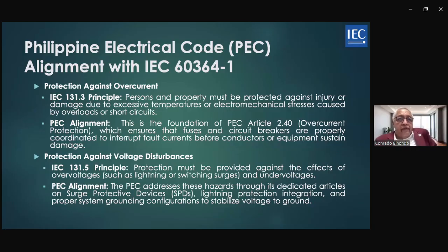Then there's the fourth one, which is very important: protection against voltage disturbances. 131.5 of IEC states that protection must be provided against the effects of overvoltages, such as lightning or switching surges, and of course undervoltage. So we need SPDs, surge protective devices, or for lightning, lightning arresters.